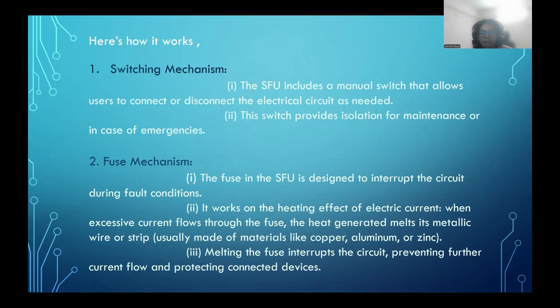There are four main working principles. One, switching mechanism. The SFU includes a manual switch that allows users to connect or disconnect the electrical circuit as needed. Two, fusing mechanism. The fuse in the switch fuse unit is designed to interrupt the circuit during fault conditions, such as the heat effect of electric current. When excess current flows through the fuse, heat is generated, hence melting the wire. When the wire melts, it prevents further current flow and protects connected devices.